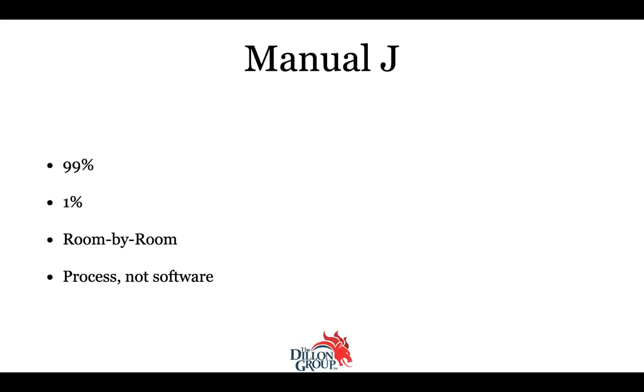And I said, hold on a minute. The reason we rejected the load calculation is because the house that was in the load calculation does not match the house that is being built. The square footages are all off. The surface areas are all off. And he said, you can't expect my guys to know how to do that. Calculating areas when you're doing a load calculation is kind of the job description, because surface areas is one of the required elements to do this. And then he started arguing with me some more.